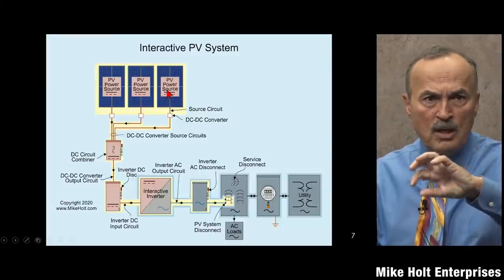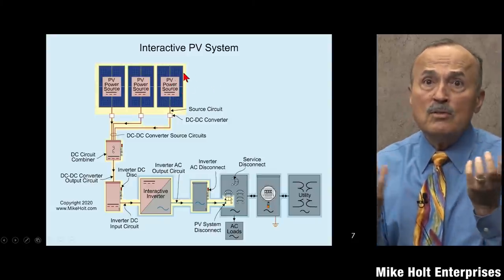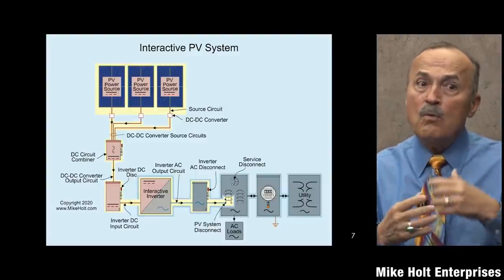Is the term 'power source' important? When we get to Article 705, we have power sources. Most electricians are dealing with just loads, but now we're dealing with power sources. Power sources include wind, solar, generators, and batteries. Transformers transform rather than being a source itself. Article 690 only talks about solar photovoltaic; wind is Article 694, and energy storage systems are Article 706.